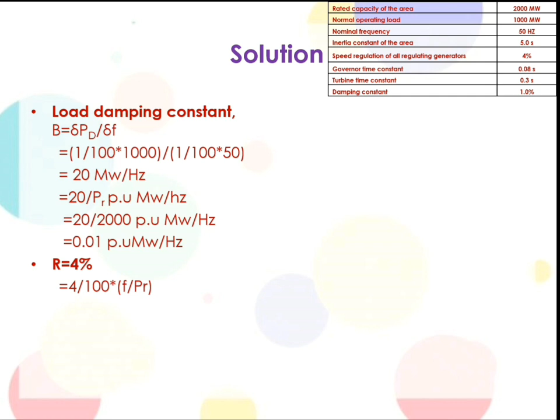R is given as 4%. Here we have to determine R in terms of hertz per unit megawatt. So it is equal to 4 divided by 100, that is 4%, into F divided by PR. F is 50 hertz and PR is the rated capacity of the area, 2000. So 4 by 100 into 50 divided by 2000 is equal to 0.001 hertz per megawatt. Here we have to obtain it in hertz per unit megawatt, so it is multiplied by 2000, the base value or rated capacity of the area. So 0.001 into 2000 is equal to 2 hertz per unit megawatt.